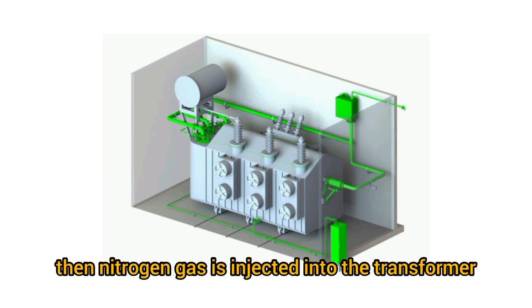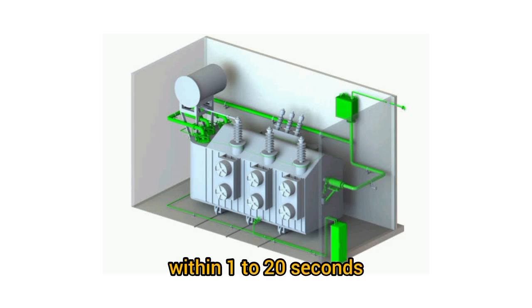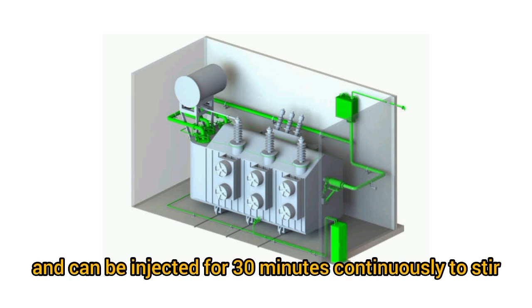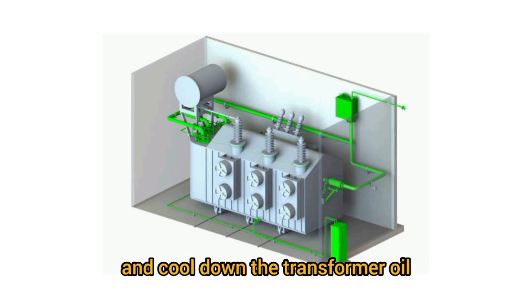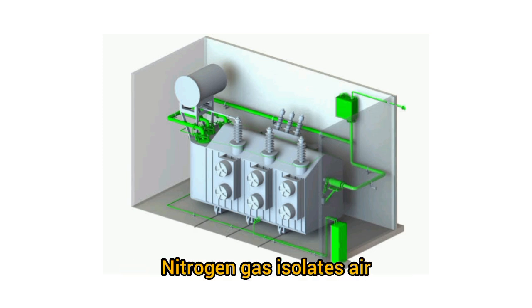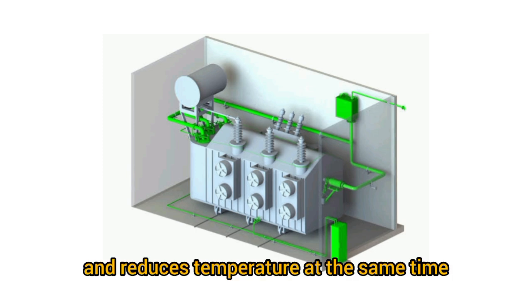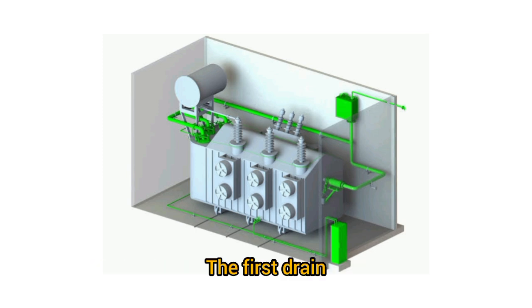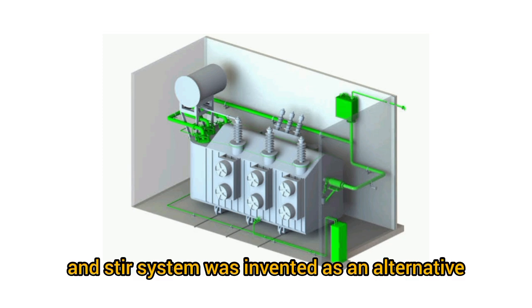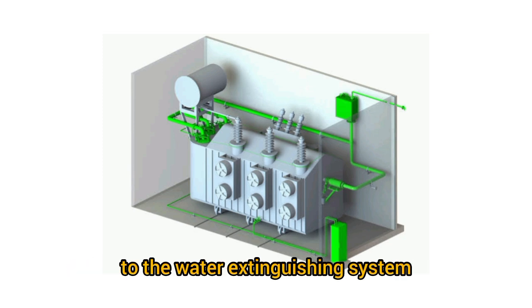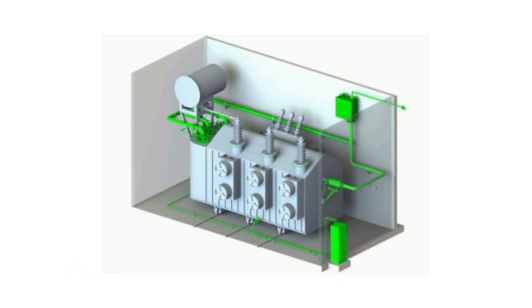Then nitrogen gas is injected into the transformer within 1 to 20 seconds and can be injected continuously for 30 minutes to stir and cool down the transformer. The nitrogen gas isolates air and reduces temperature at the same time. The first drain and stir system was invented as an alternative to the water extinguishing system.